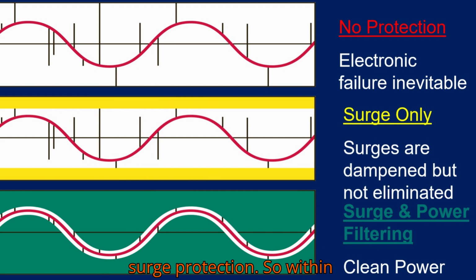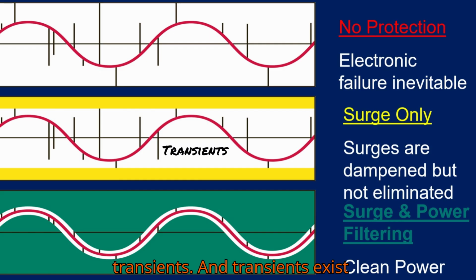So within that protected zone, in the day-to-day alternating current, there can still exist millisecond spikes of electrical current that don't reach the threshold of your power surge protection, yet are still a spike in electricity. These millisecond micro spikes, or micro surges, are in technical terms called transients, and they exist every day.